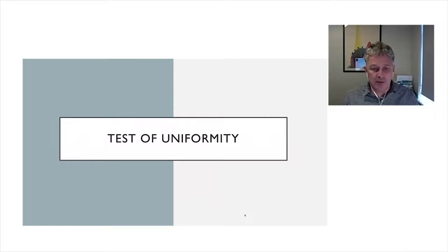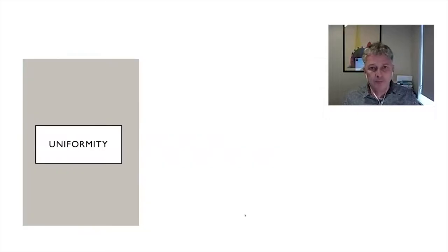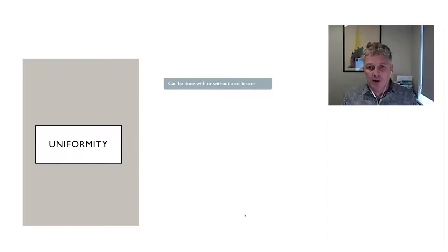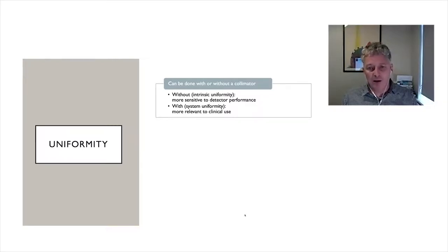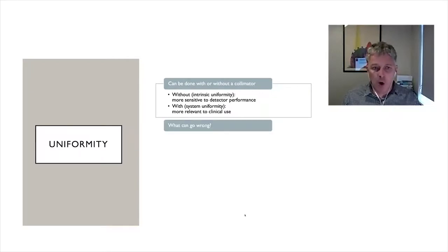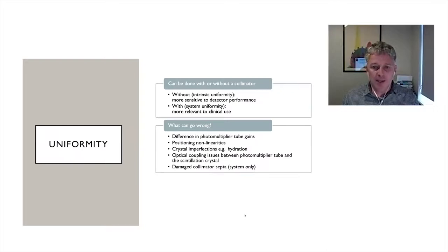Let's start with the test of uniformity. Uniformity is often done with or without a collimator. Without a collimator, it is more sensitive to detector performance issues. With a collimator, it is more relevant to clinical use. What can cause bad uniformity? It's important to consider what the underlying issues might be.